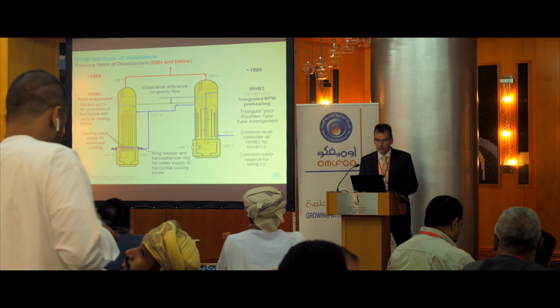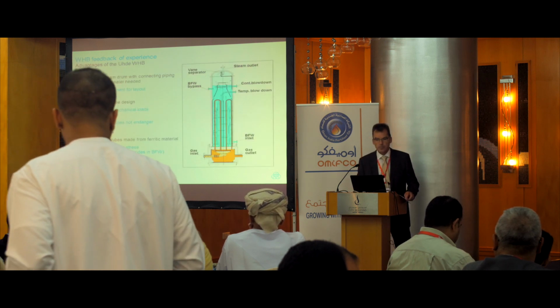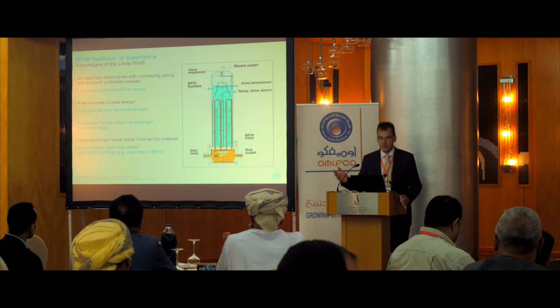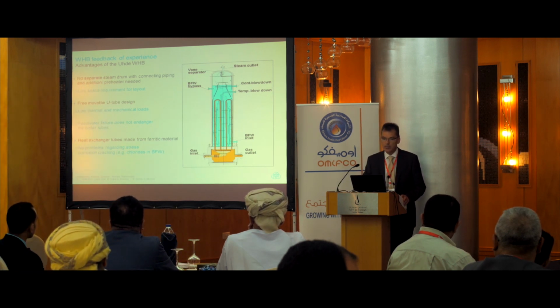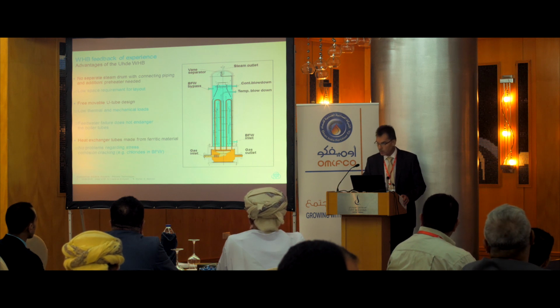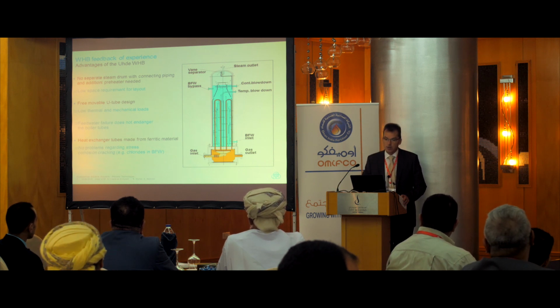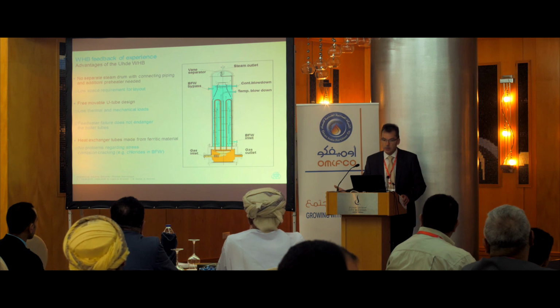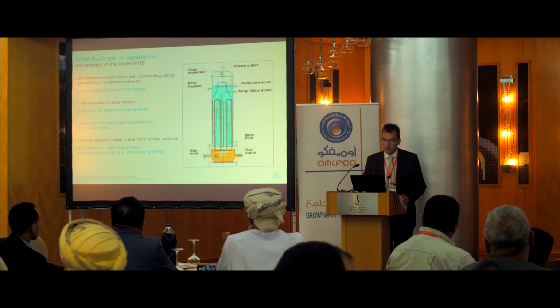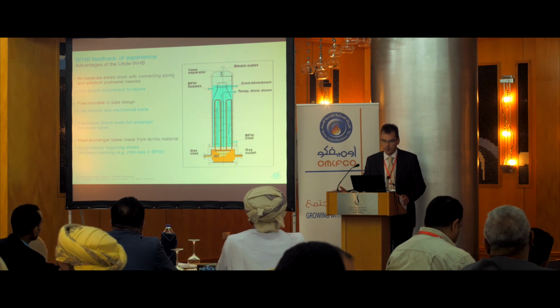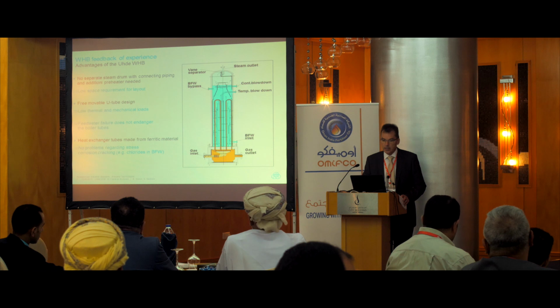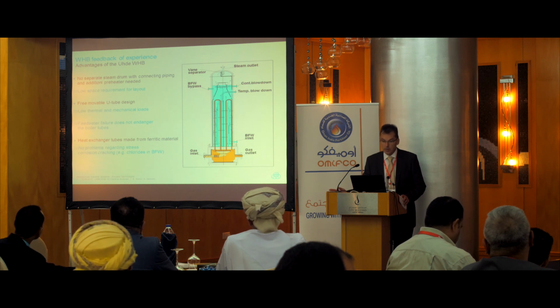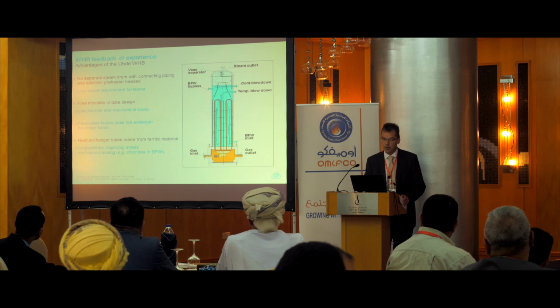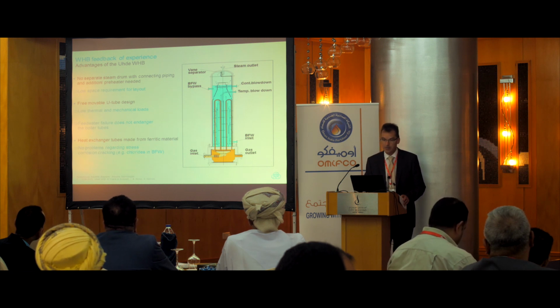What are the advantages of these waste heat boilers? First of all, we have no separate steam drum with connecting piping and additional preheater needed. That means low space requirement for layout. We have free movable U-tube design. That means low thermal and mechanical loads on the tubes. And feed water failure does not endanger the boiler tubes. And the heat exchanger tubes are made from ferritic material. That means no problem regarding stress corrosion cracking if we have some chlorides in the boiler feed water, which we don't like anyhow, by the way.